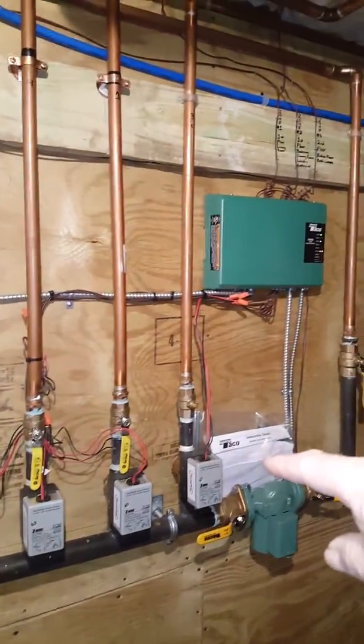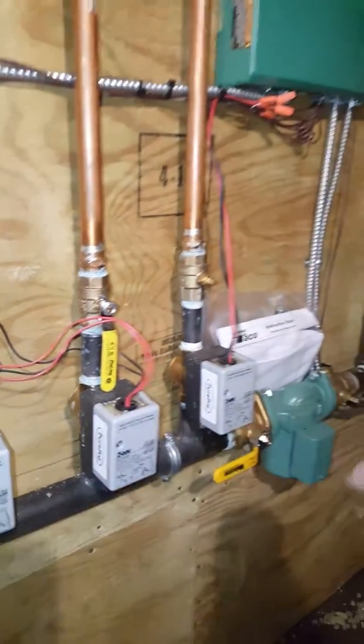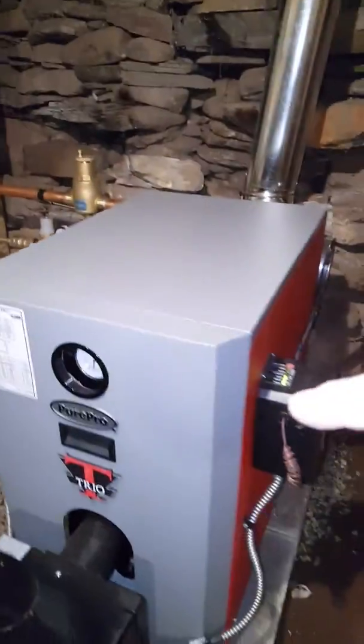And then we have our main control, which is your Taco zone control. Anytime a zone calls for heat, it opens up one of the zones here, turns on the circulating pump — high velocity circulating pump — and then turns the boiler on.